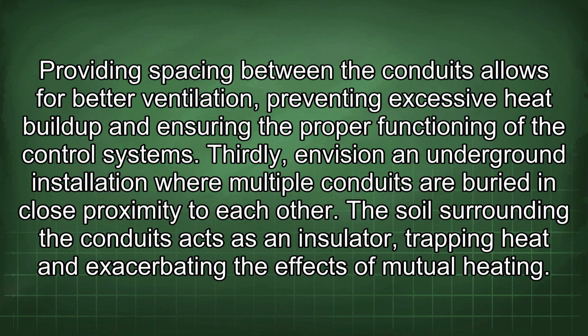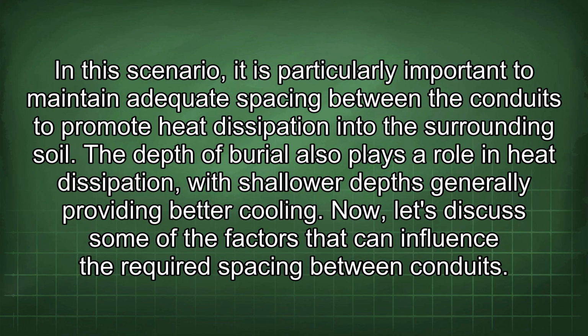control systems. Thirdly, envision an underground installation where multiple conduits are buried in close proximity to each other. The soil surrounding the conduits acts as an insulator, trapping heat and exacerbating the effects of mutual heating. In this scenario, it is particularly important to maintain adequate spacing between the conduits to promote heat dissipation into the surrounding soil. The depth of burial also plays a role in heat dissipation, with shallower depths generally providing better cooling.